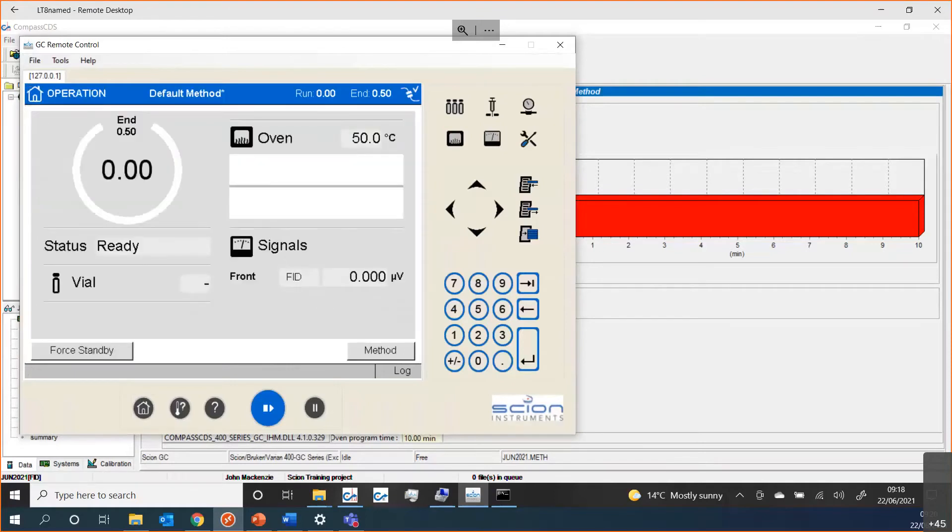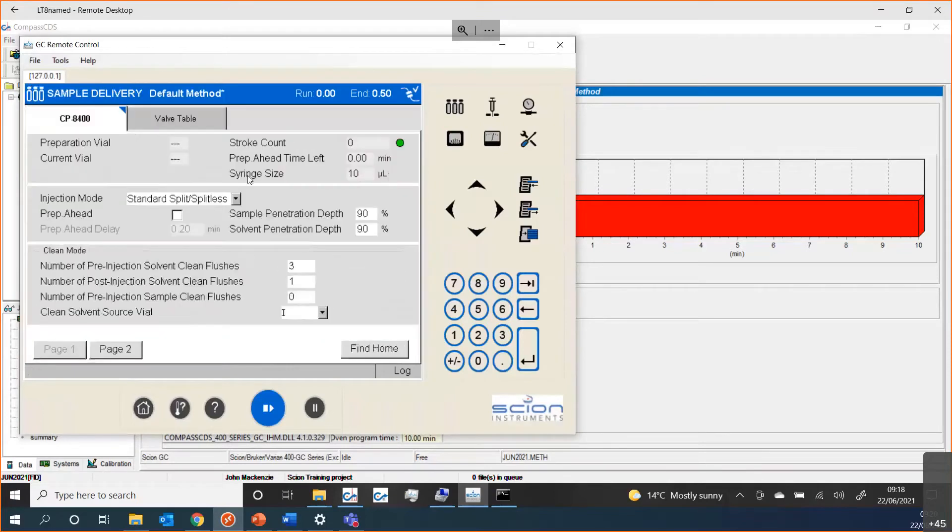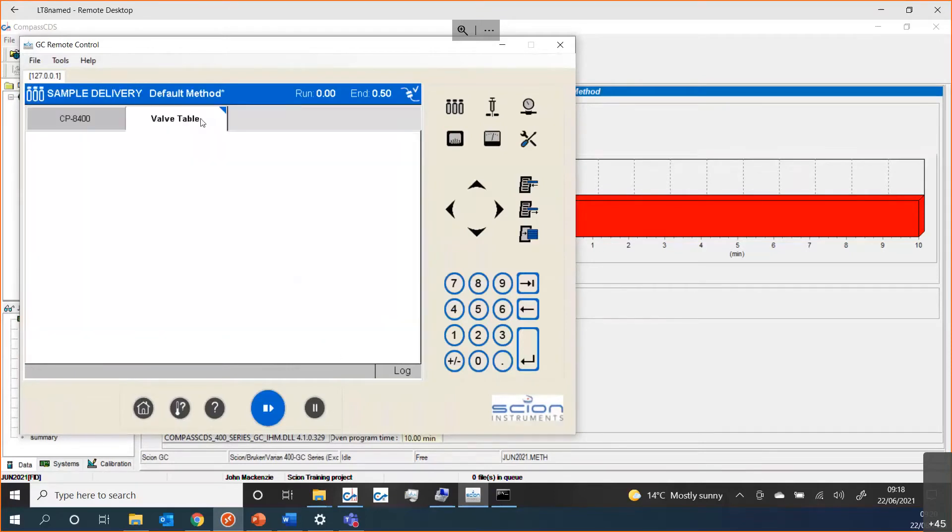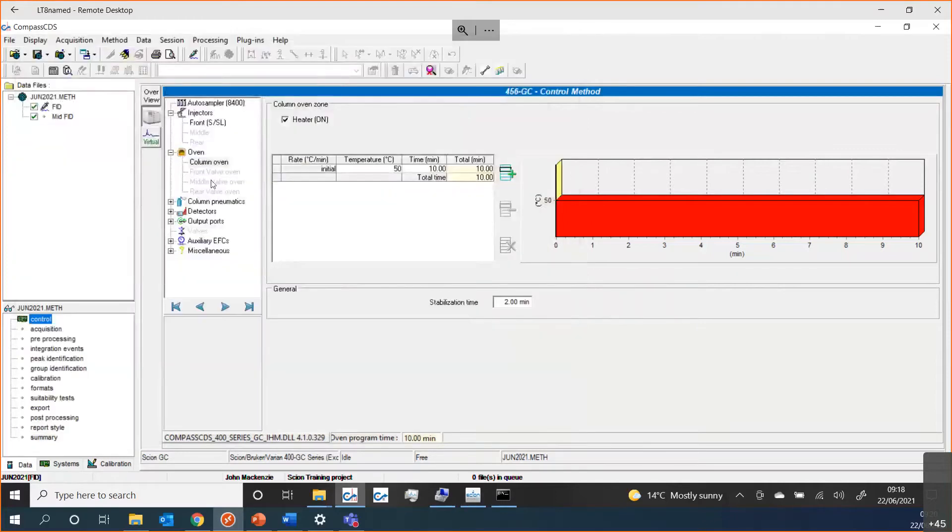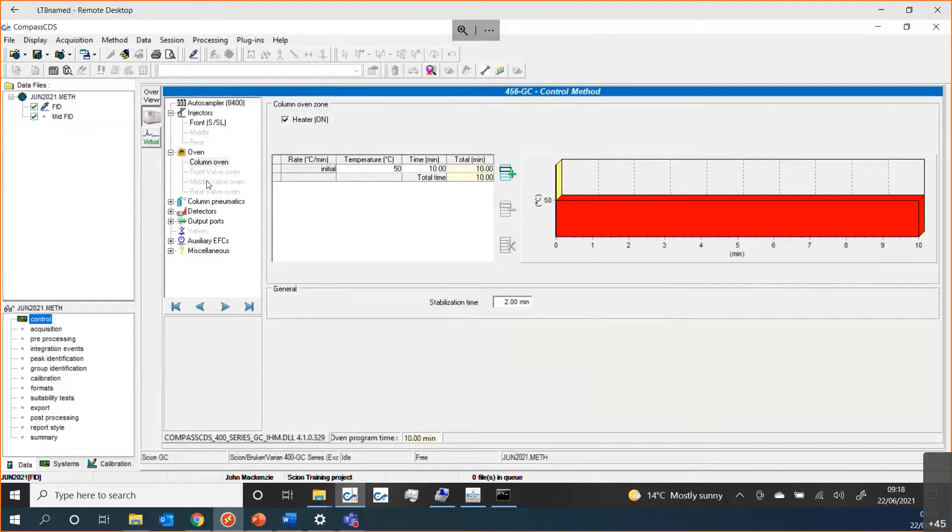If we go through some of the sections of the method, if we look at the control section of the method, you can see all of the different aspects of the GC are populated here. These reflect what we see in the actual GC. If I do home, you can see I have an auto sampler, I don't have any valves, what injector I may have. These are reflected in my method because the configuration of the GC is pulled through as part of the setup process within Configuration Manager.